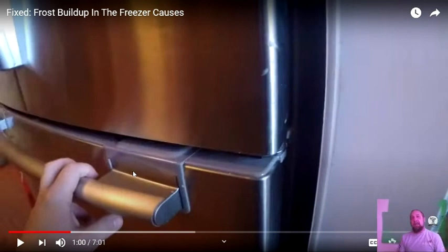If you tug on it, it should give a little bit of resistance and the whole bill shouldn't just fly right out. What you want to do is close the door about halfway on the bill, like on the face of George Washington, for example, and you tug on it lightly, just keep tugging on it. It's sort of like someone else has two fingers holding the other end of it as you're tugging it through their fingers. Then that's a good seal.